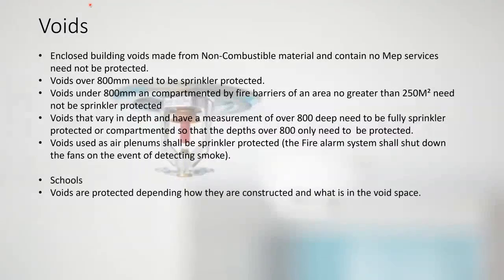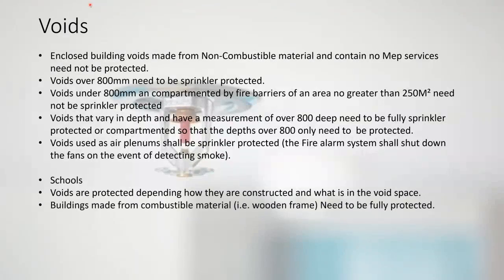And in schools, voids are protected depending on how they're constructed and what's actually inside the void space. Buildings made from combustible materials, wooden frames, need to be fully protected no matter what's in the void space.